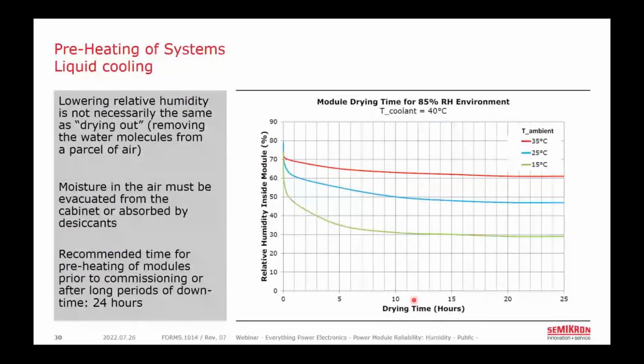So what we have here is a liquid-cooled power module that has been held in an 85% relative humidity environment until the relative humidity down at that chip level has reached 85%. What I'm showing here is the results of an experiment very similar to what we showed earlier, except we're on a liquid-cooled heatsink. And this condition of having high relative humidity inside the module could be the situation if the power modules were transported through a high humidity environment, like a tropical environment by ship or whatnot, or if the power modules have been sitting unpowered for a long time in an outdoor environment. For example, in a wind turbine power converter that has undergone maintenance for some days and is not under operation.